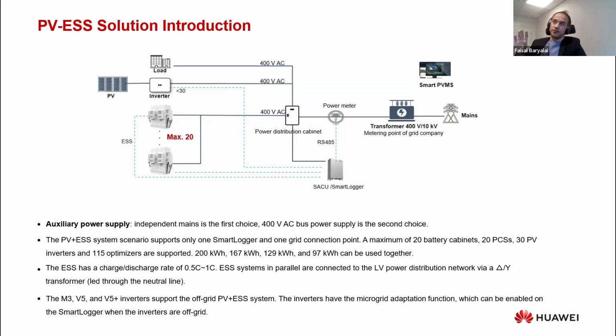So this is the general configuration: say we have a PV system, inverters, and also an energy storage system. This is how we can connect it, with one grid connection point at 400 volts. This is the simplest configuration, and we can put up to 30 inverters in such a system.